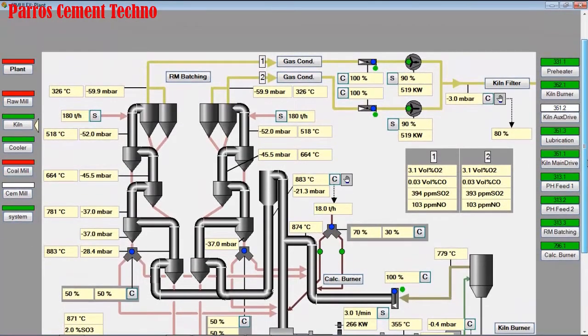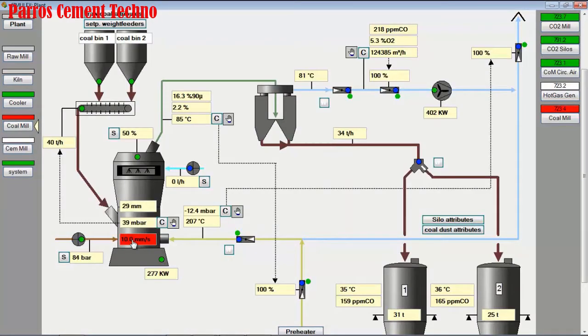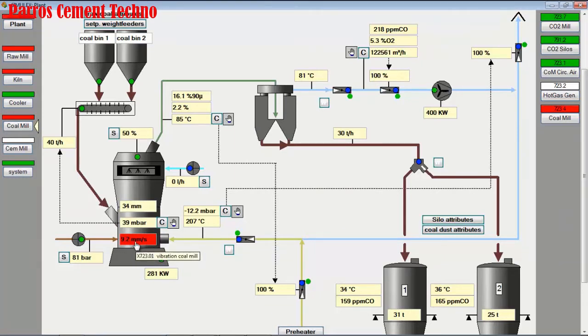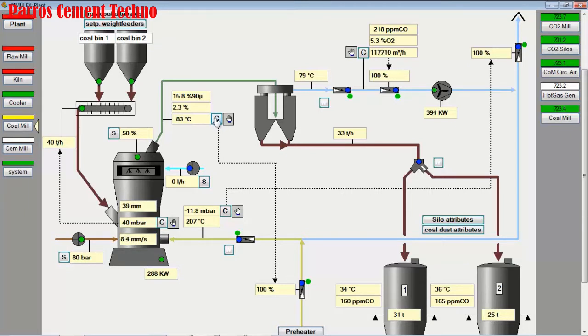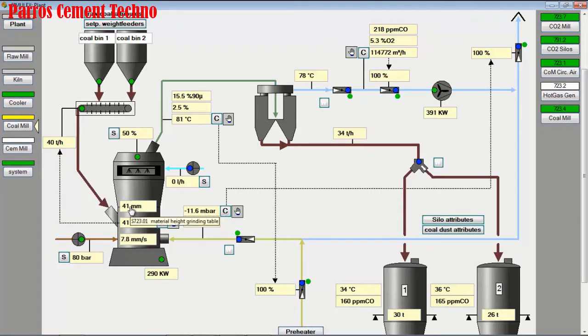Looking at the coal mill display, there is an alarm. The mill vibration is high because the low bed material causes the vibration to increase. We must try to reduce the mill vibration as soon as possible so that the mill does not stop.